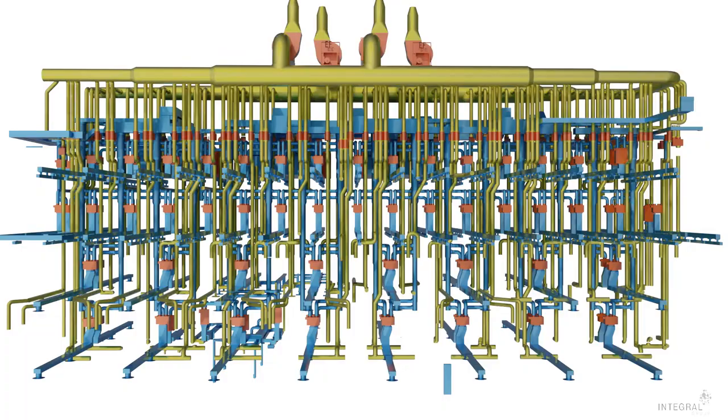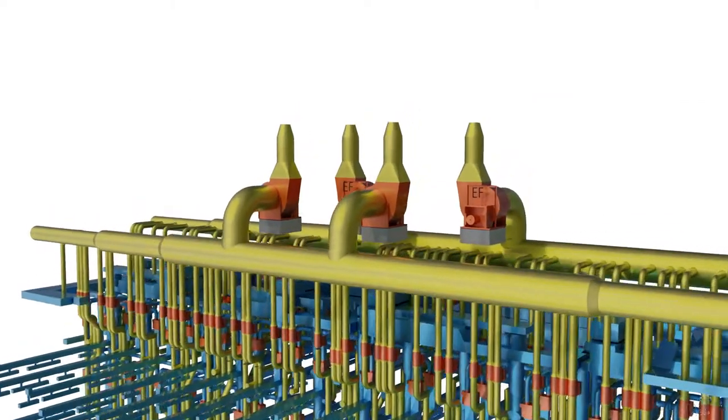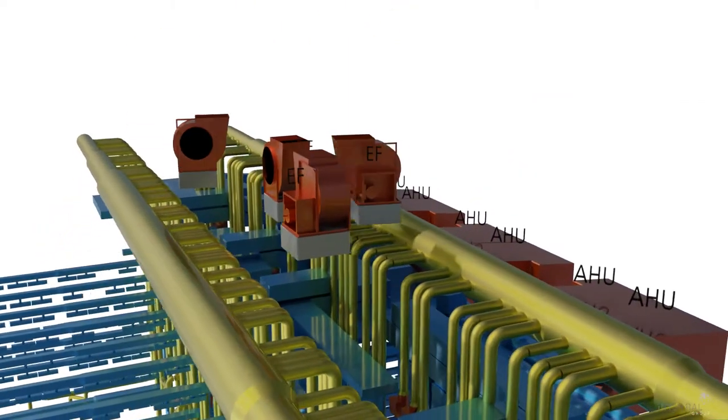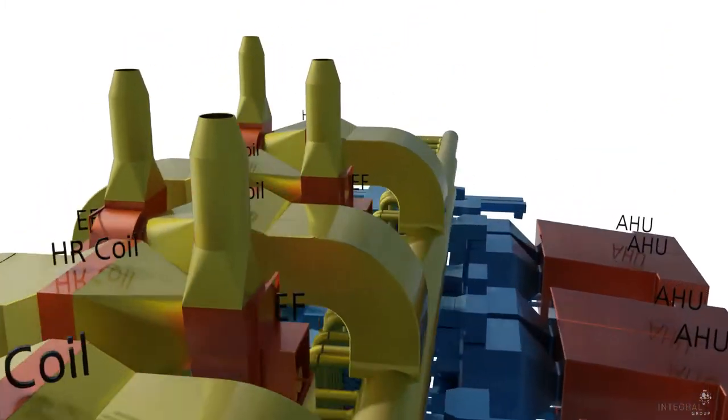Every exhaust valve was ducted up to exhaust headers on the roof. For phase one of the renovation, we reused the existing exhaust fans, fit them with variable frequency drives, add another fan for redundancy, and then add heat recovery coils.